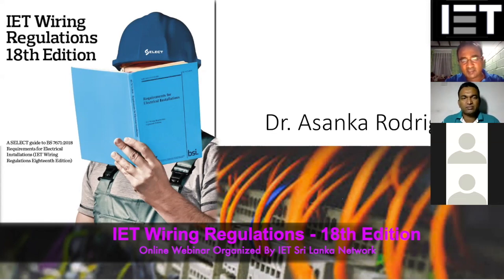Then what is the maximum ground potential rise, GPR, allowed? There is no such requirement mentioned in the regulation, as I know. The ground potential rise depends on your resistance and the amount of the fault current. If you are maintaining the safety requirements, it doesn't matter, because everything will rise, like when you are standing on the same potential. The only thing is you cannot maintain two potentials. So there is no limit; it can go to whatever value depending on your fault current, or the current you are diverting to the ground.